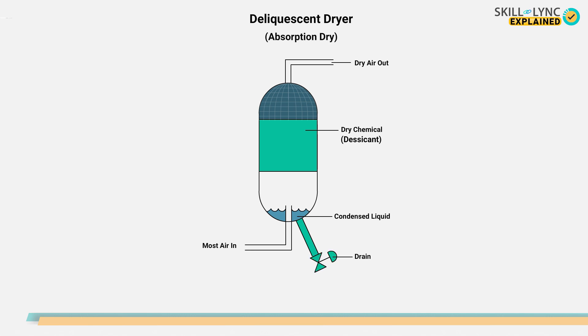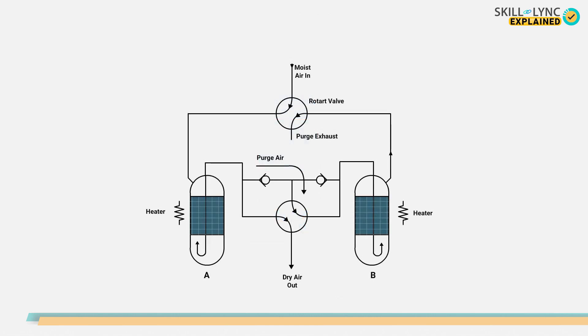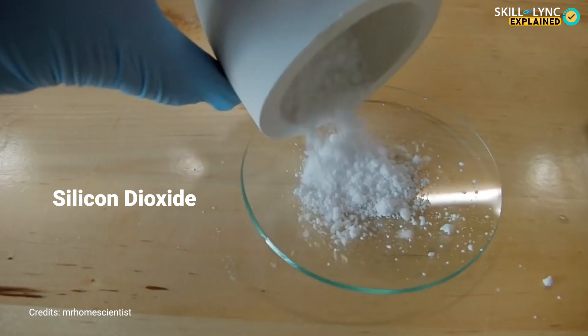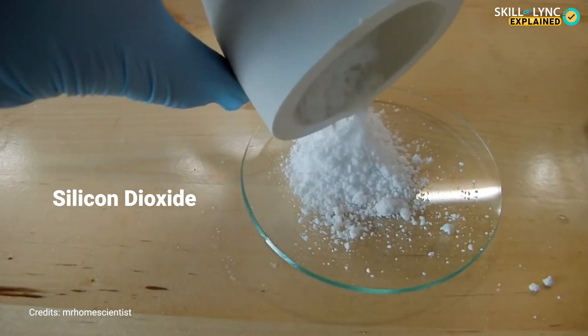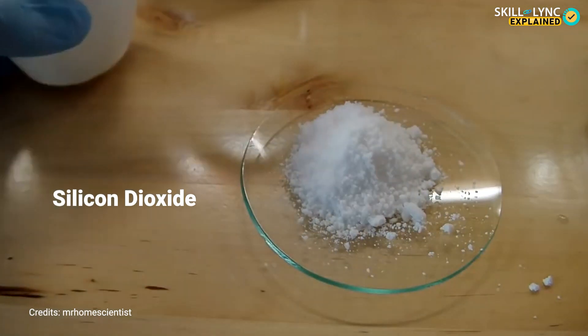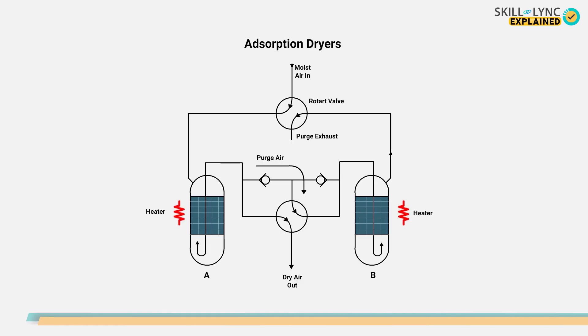These types of dryers are called absorption dryers. Since they use a chemical that is used up in the process, they need to be replaced at regular intervals. This problem of replacement is overcome by using adsorption dryers, which use a granular material such as silicon dioxide that collects moisture on its sharp edges. This moisture can be released back by simply heating the material.